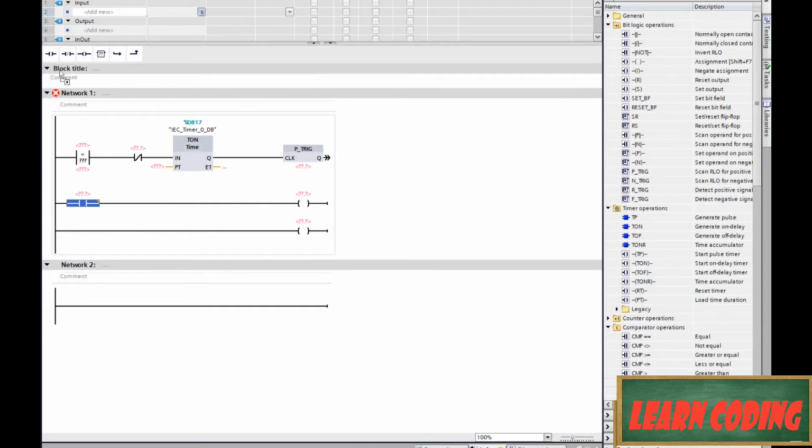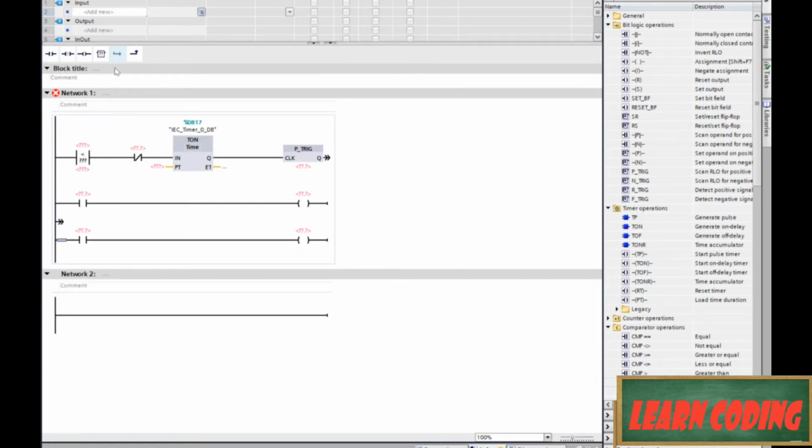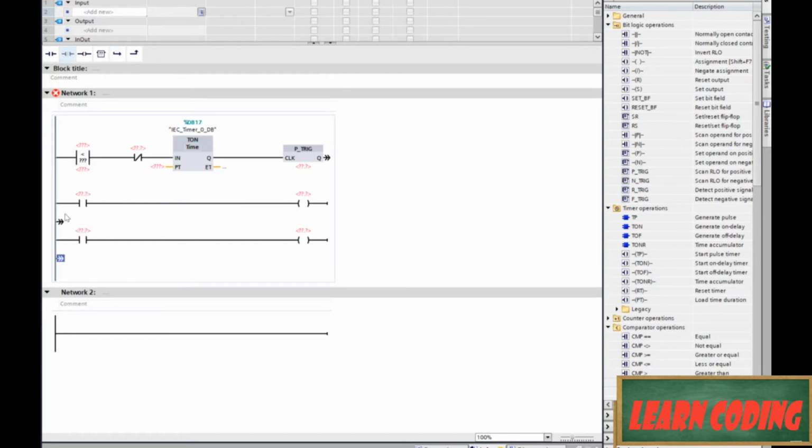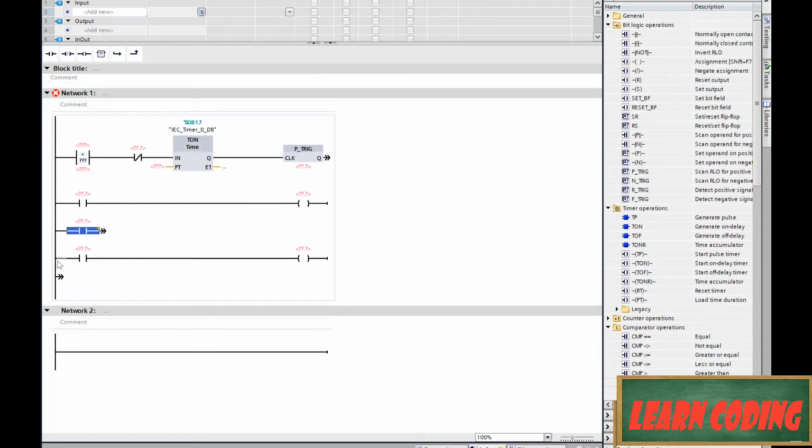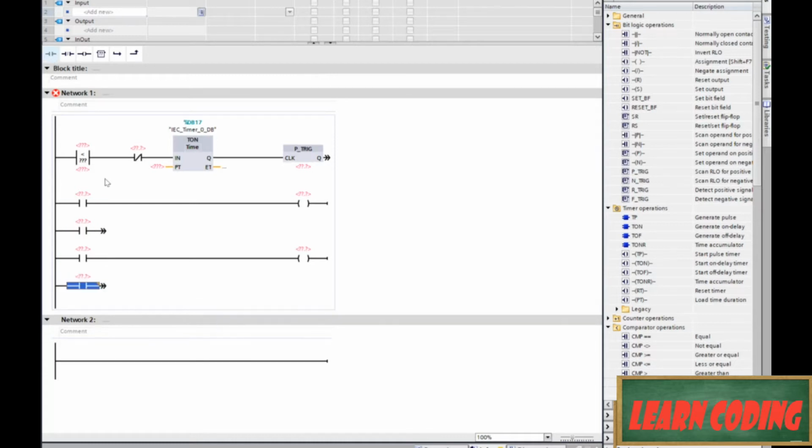I know each one of those is going to be triggered by my trigger. And then for each one of those, I know I need some digital control logic. And that's going to consist of a hold-in on each one of those. My notification can be reset by 2 things. And my actual alarm bit can only be reset by 1. All right, so I think I can just connect those up. There, that's my basic alarm structure.